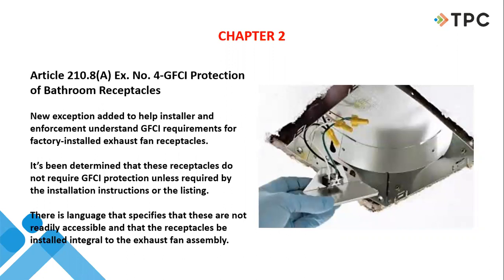Little exception to the ground fault requirements. Apparently there was a lot of, I'll say what it was, I wasn't there, but I'm going to say what I know, a lot of arguing back and forth between installers and inspectors as to whether or not that little receptacle in the exhaust fan in a bathroom requires ground fault protection. Says here, it's been determined that these receptacles do not require ground fault protection unless required as part of the installation instructions or the listing that comes with the fixture. These aren't considered readily accessible, and they're installed integral to the exhaust fan assembly. So they're not too excited about whether or not ground fault protection is provided for these little guys. And I agree with it 100%.